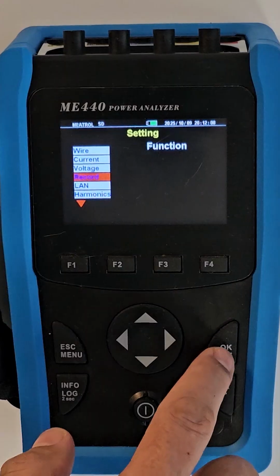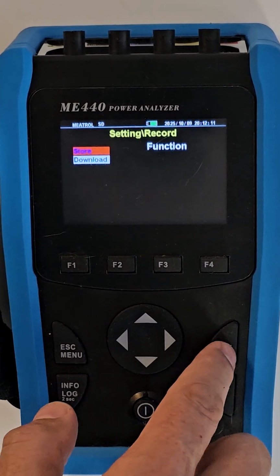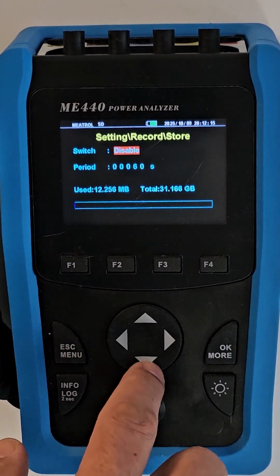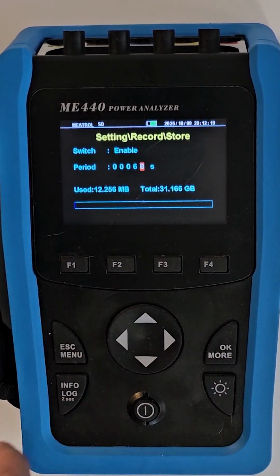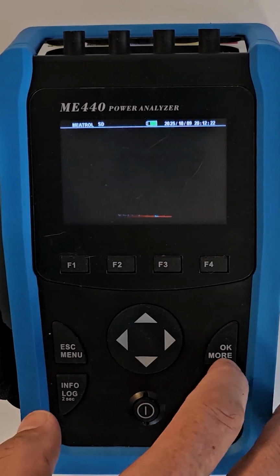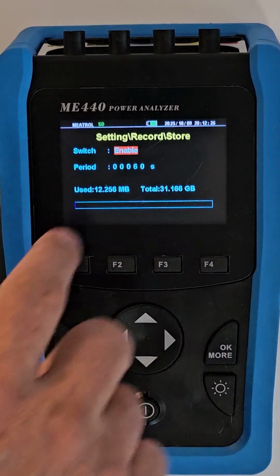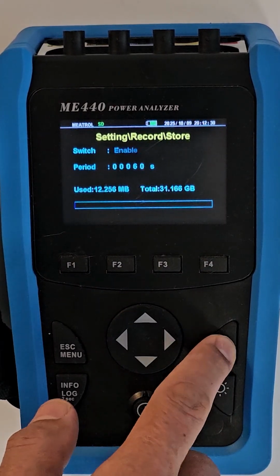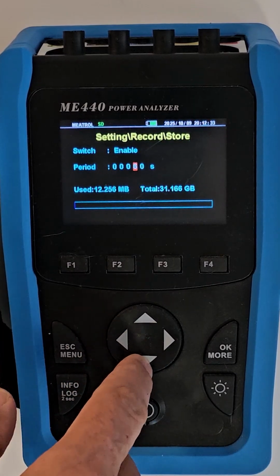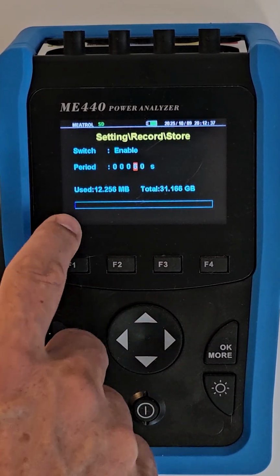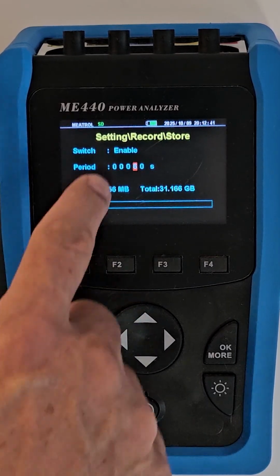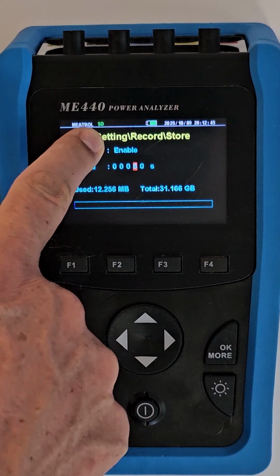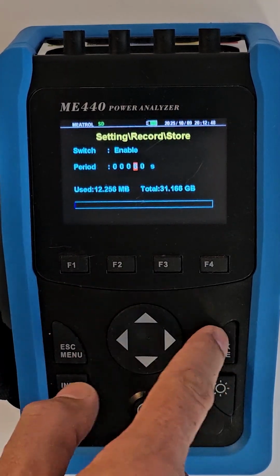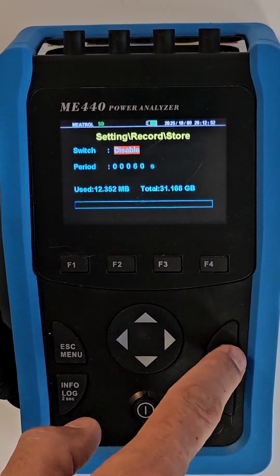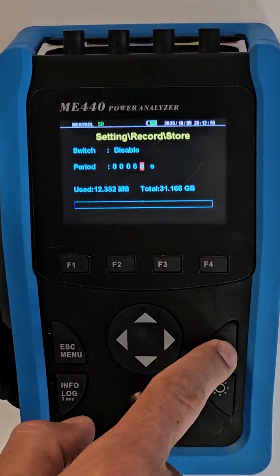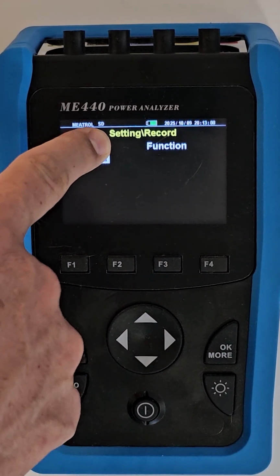Okay, so if you go into the record screen and then store, you can either disable it or enable it. So if it's enabled, it means as soon as the meter is turned on, it will start recording at the set interval or set period. So in this case, each 60 seconds. You can change that to be more or less by using up and down buttons. You also notice that if it's enabled, the little green SD sign is green. And if we disable it and save it, you'll see the SD sign is back to white.